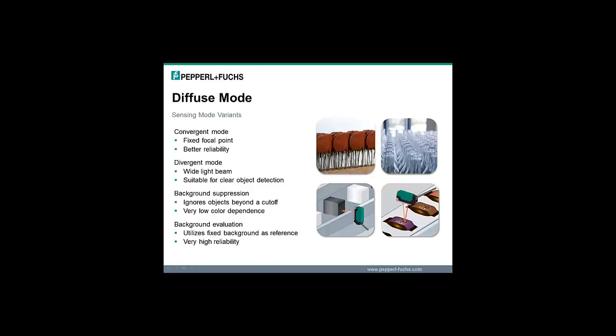Diffuse mode sensors have several special variations designed to overcome some of the limitations associated with diffuse mode sensing. Convergent sensors have a fixed focal point to provide better reliability compared to basic diffuse sensors. Divergent sensors have a wide light beam that is very sensitive to minor differences in received light and are suitable for clear object detection. Background suppression sensors detect objects up to a designated cutoff point and ignore objects beyond, with high reliability and very low dependence on object color. Background evaluation sensors utilize a fixed background as a reference and also have very high detection reliability.